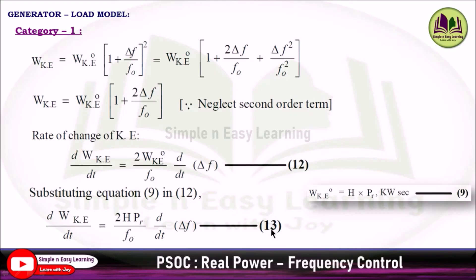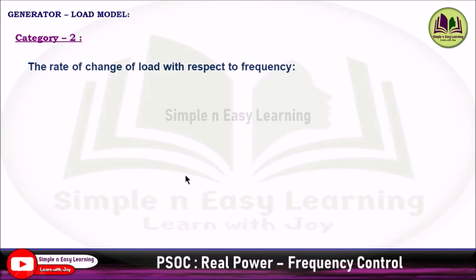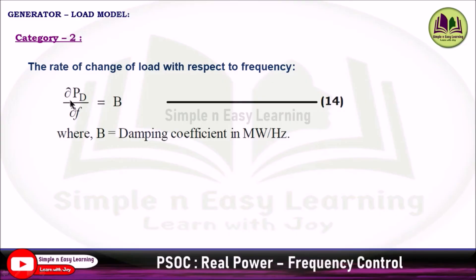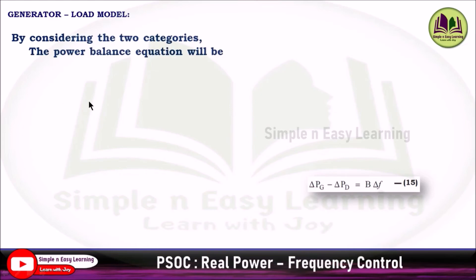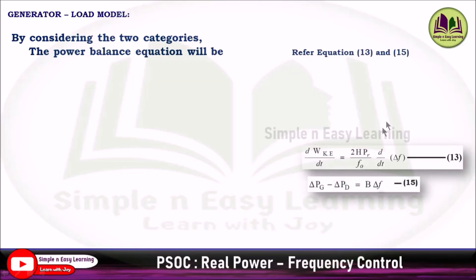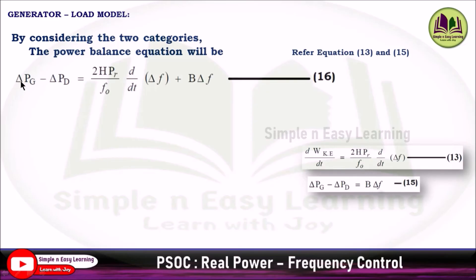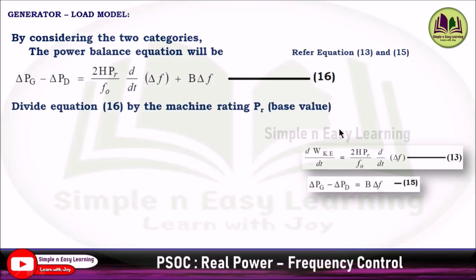Category 2: the rate of change of load with respect to frequency is ∂Pd/∂f = B, where B is the damping coefficient in MW/Hz (Equation 14). The damping coefficient has a positive value for motoring load, giving del_Pg − del_Pd = B·del_f (Equation 15). Combining both categories, the power balance equation is: del_Pg − del_Pd = (2H·Pr/f₀)·d/dt(del_f) + B·del_f (Equation 16).